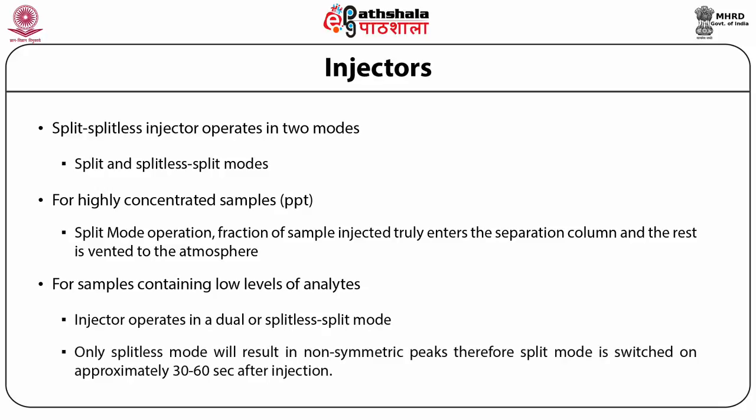If the splitless mode is continued throughout the run, the peak will be non-symmetric and will interfere with peak integration. To overcome this problem, split mode is switched on approximately 30 to 60 seconds after injection. This dual splitless-split mode permits the majority of the sample to load onto the column while clearing remaining samples to allow for a clean, well-shaped chromatographic peak.